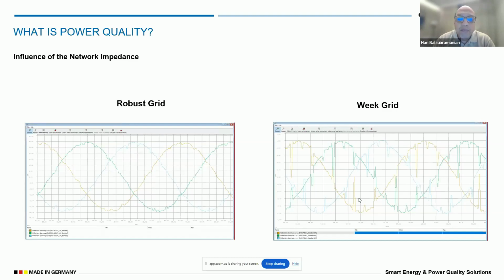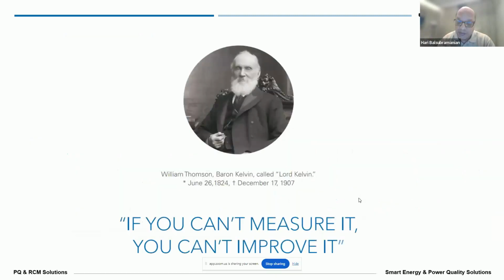Yeah, so this is the robust grid. In many places, if we have a very good grid, then we can also throw some harmonics, which is essential for us to make our efficient systems with some kind of VFDs or drives, so that we get a higher production. But if the grid is weak and you use the same kind of equipment, then it can potentially not only affect us, it can also affect the nearby consumers. So that's the part which I wanted to put across.